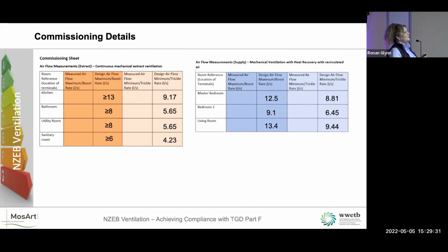And this is where the confusion starts when I'm giving the course, because Part F talks about general ventilation and it talks about boost rate. You go to fill it in on the commissioning sheet, and they talk about design airflow minimum or trickle rate, and then design airflow maximum or boost rate. And it's throwing the cat among the pigeons there big time. So this on the right, and you read it from right to left for some reason, is your general ventilation rate. You calculate them, you fill them in those boxes.